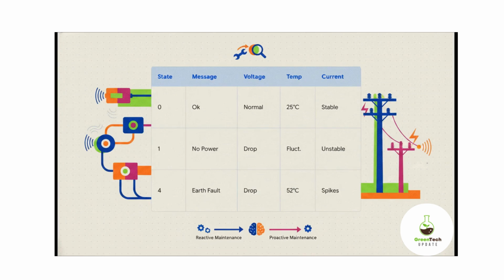This hard data fundamentally changes the game for maintenance crews, translating raw vital signs into actionable intelligence. For instance, state 0 is normal: the system is okay, oil temperature sitting at a comfortable 25 degrees Celsius. But jump down to state 4, an earth fault, and immediately the voltage partially drops and you see sudden, dangerous current spikes.